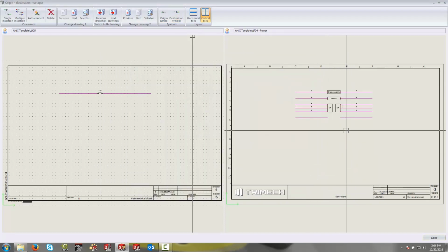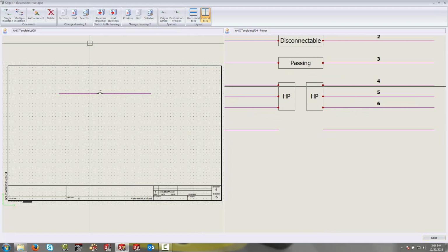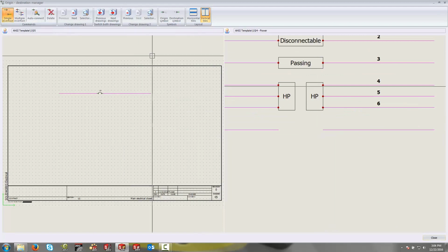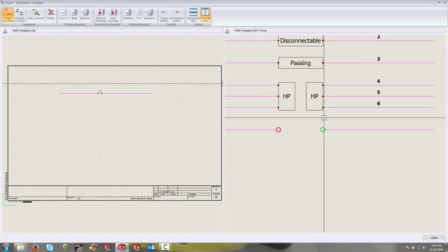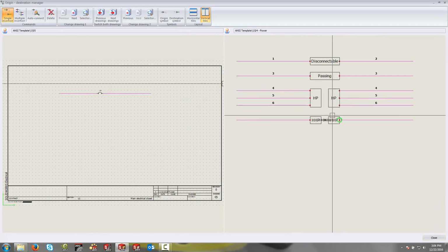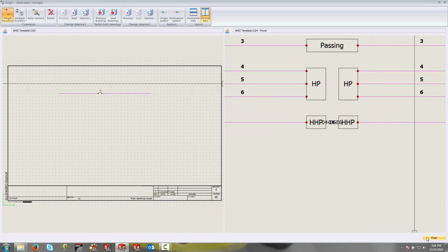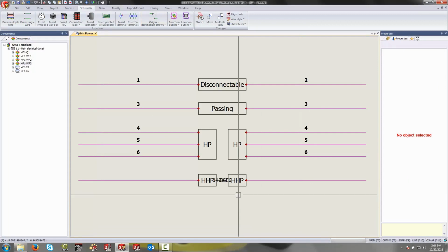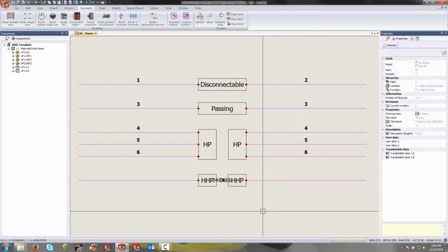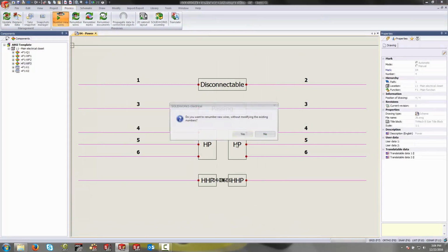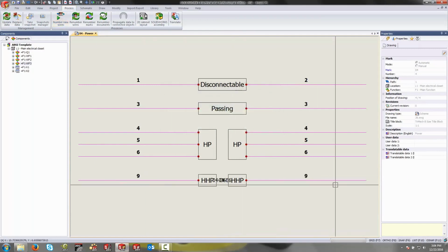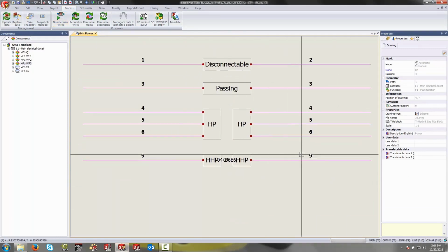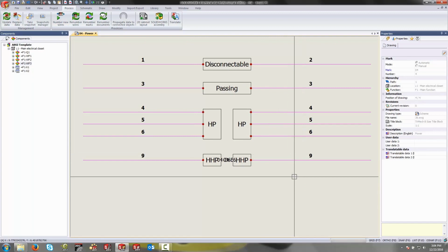And by doing that, when I come over to this page here, I'm going to do a single insertion to connect this wire to this wire. And that will put those symbols into place. Now when we pop back to our schematic, I can go ahead and, well, we can just say number new wires. And you'll see it's going to pass that equipotential number from one side to the next.